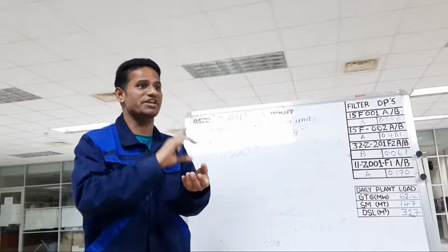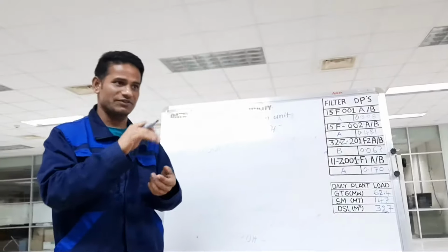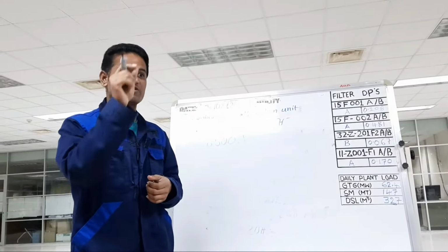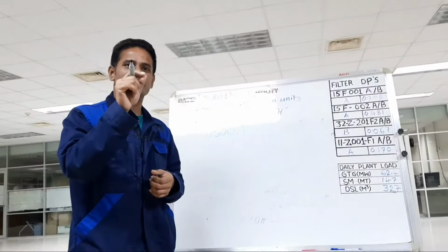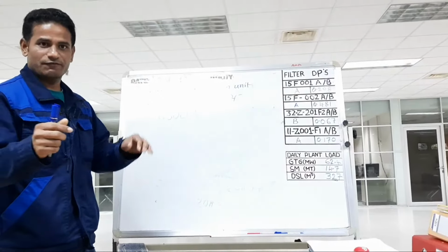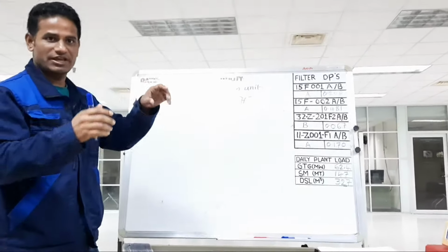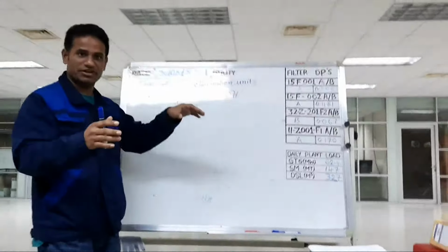But in the hypochlorite storage tank we are using a blower, and this hydrogen is also going, and all this product going into the hypochlorite storage tank. At that time some bubbles and foaming are created. If like this, the level will fluctuate. So for that reason we are using another circulation line. Continuously we are using 10 meter cube per hour of feed water for breaking down the bubbles, and after that all this product goes, and on the blower side air also comes, and after this the hydrogen is removed from the top side.